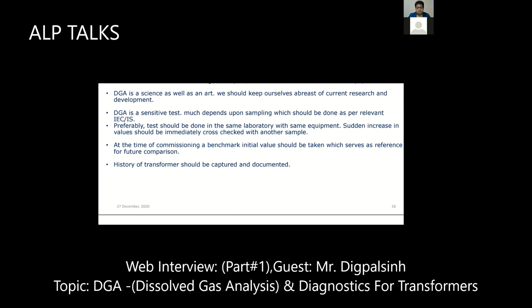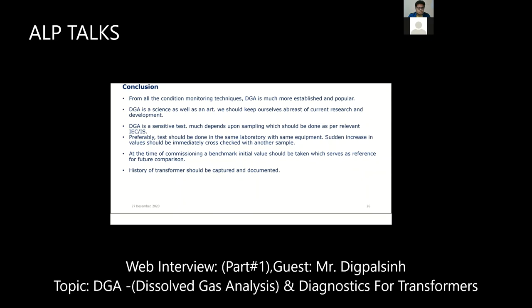It is mainly defined for the DGA oil sample, because it also matters how you took the sample. At the time of sample taking, it is exposed to the air or sunlight. Your transformer may be healthy, but when you took the sample, it looks unhealthy, because some gases from the atmosphere will come in at the time of taking the sample. Benchmarking at the time of commissioning, initial values should always be taken. Nowadays it is a common practice for all utilities and the private sector. They always do DGA before commissioning.